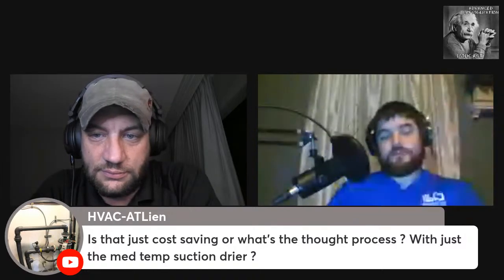Is that just cost savings, or what's the thought process with the medium temp suction dryer? It's just their design. There's no cost savings. That's how Advancer designs it. They figure there's so much velocity coming back through the medium temp suction that's where they're going to catch the majority of their stuff. And they use a Y strainer with a really thin, really fine screen on the liquid going out, so they're going to catch everything from that. Most CO2 racks have fewer contaminants in there, especially if you're purging, until the compressors start blowing apart.